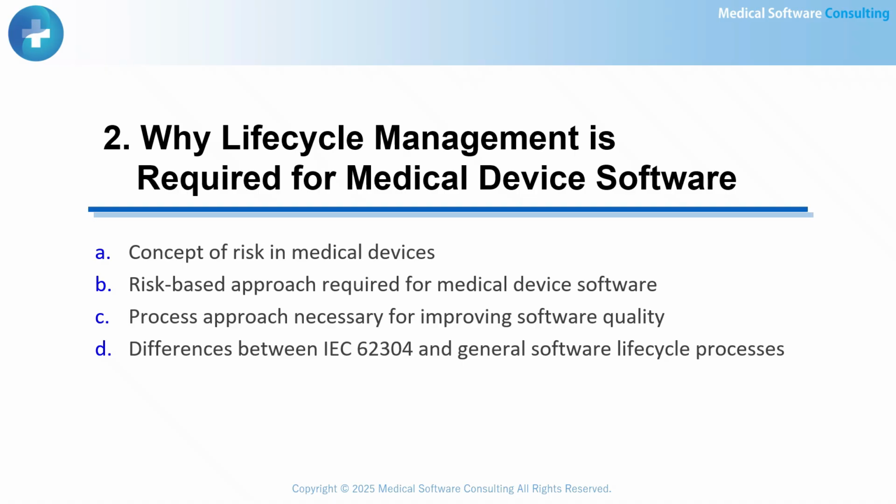Finally, we will look at the differences between IEC 62304 and general software lifecycle processes. IEC 62304 is tailored for medical devices, with a stronger focus on risk management and patient safety. Together, these points explain why lifecycle management is not optional, but a fundamental requirement for medical device software.